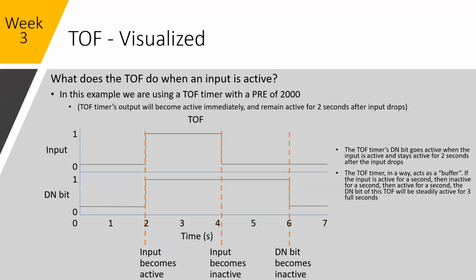Let's say there's a multi-stage for disabling a piece of equipment. You can press a single button, immediately fire your timer, and on release of the button, you can set your off timer to give enough time for a piece of equipment to move before the cylinder is retracted or extended. Any questions?